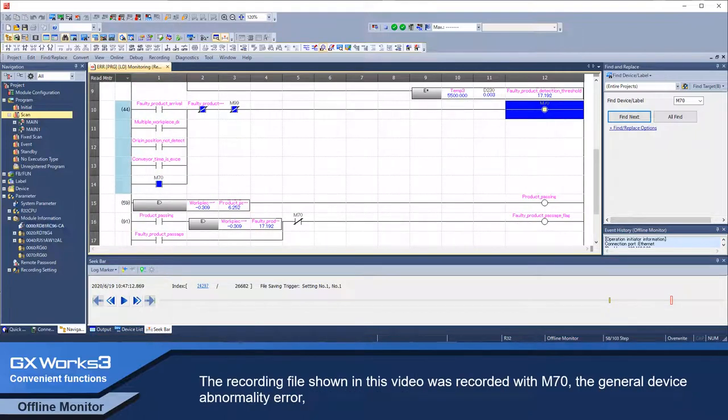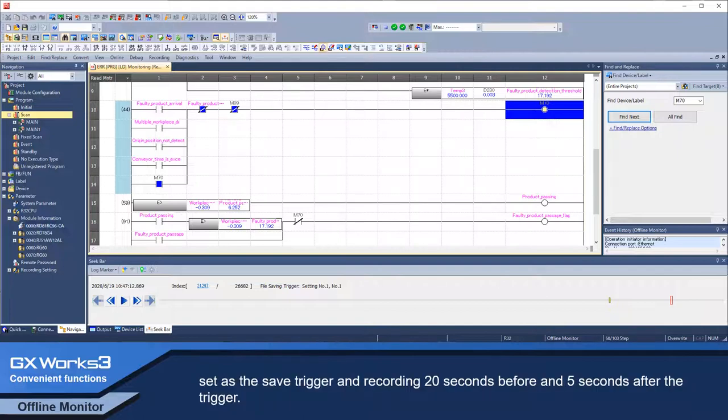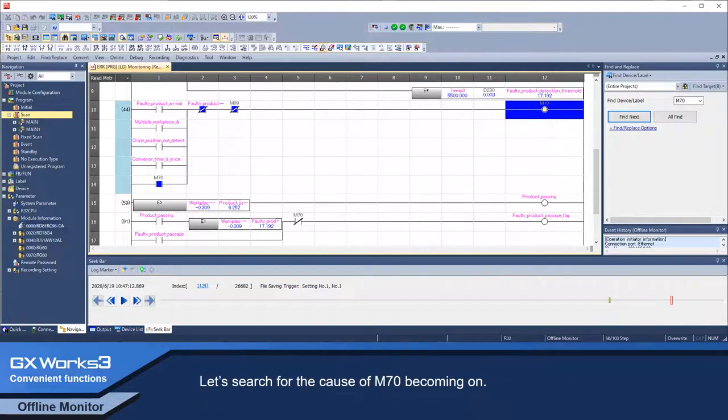The recording file shown in this video was recorded with M70, the general device abnormality error, set as the save trigger and recording 20 seconds before and 5 seconds after the trigger. Let's search for the cause of M70 becoming ON.